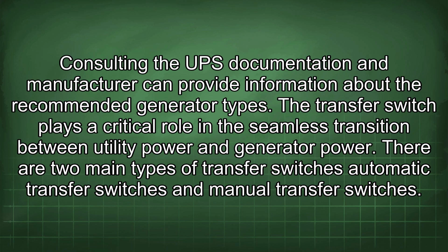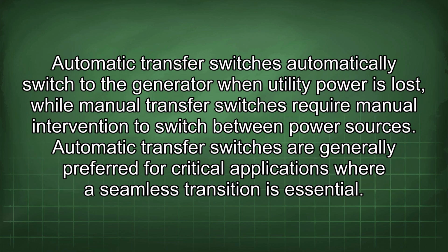The transfer switch plays a critical role in the seamless transition between utility power and generator power. There are two main types of transfer switches: automatic transfer switches and manual transfer switches. Automatic transfer switches automatically switch to the generator when utility power is lost, while manual transfer switches require manual intervention to switch between power sources. Automatic transfer switches are generally preferred for critical applications where a seamless transition is essential.